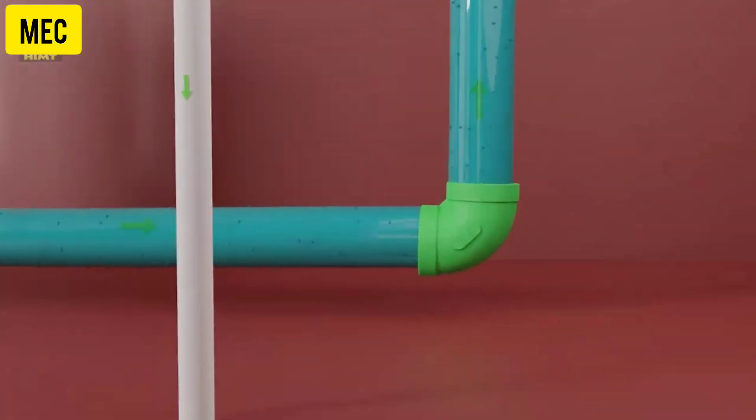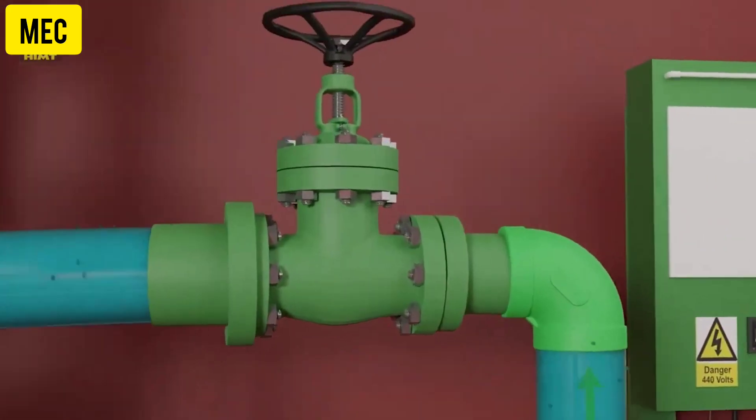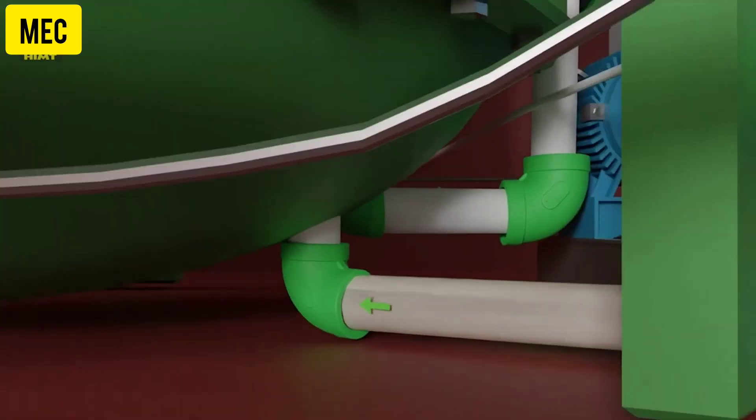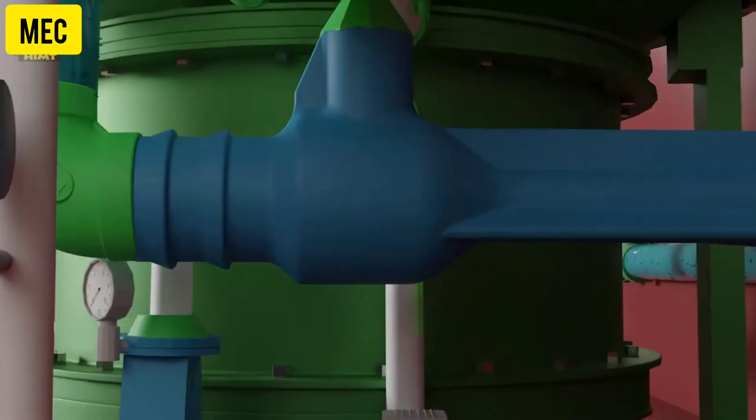Now note the ejector pump suction and discharge side pressures. And then open the seawater feed inlet valve to the evaporator. The seawater, as it flows through the ejector, sucks the air and the brine from the shell due to Bernoulli's principle.